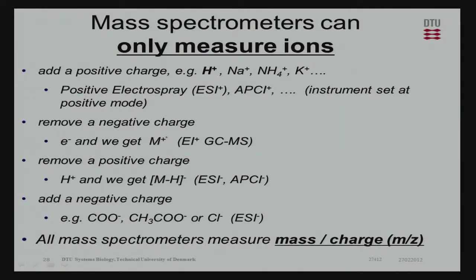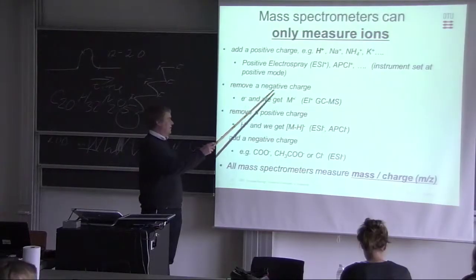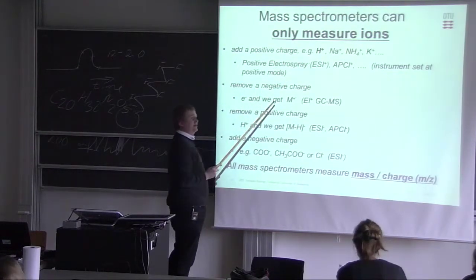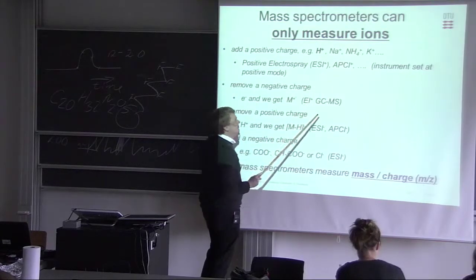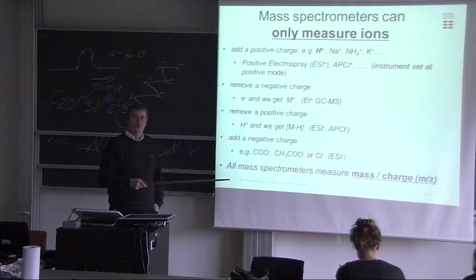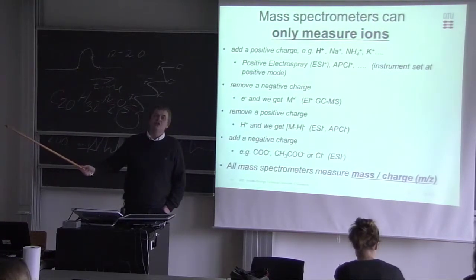So a very important thing about a mass spectrometer is it can only measure ions. It means that most of the things we are working with are neutral molecules, so we have to ionize them. If we don't ionize them, we don't see them. So the first step going to the mass spectrometer is simply the ionization chamber. We can analyze and we can add charges in various ways.